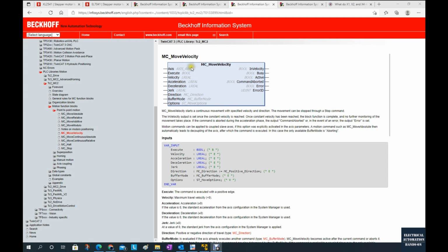For example, if we are controlling one VFD or one servo motor, the motor speed is controlled by a PID. The PID output needs to adjust the VFD or the servo motor in time, right? So this speed set point is changing on the fly. Once you get the trigger, the speed is transferred inside this function block and delivered to the axis. However, before it reaches the first command, it cannot receive the second command. So this axis cannot change on the fly. This is a big issue.